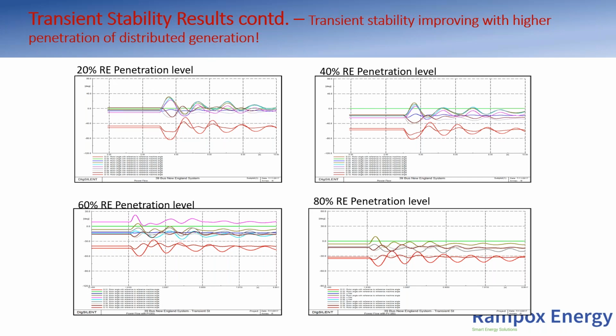It was found that at 80%, you can see the correlation in the attenuation of the rotor angle response. Comparing the graphs, at 20% the bigger swing is just below 40 degrees. Increasing to 40% renewables, the first positive swing we see is now below 20, half of that. If you zoom in, it's below 20, so it's attenuating.